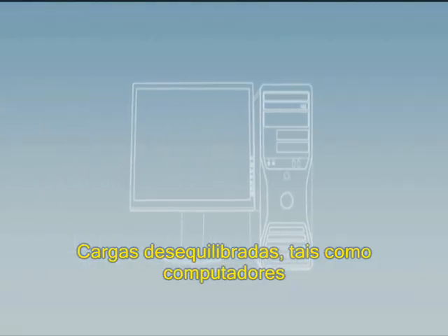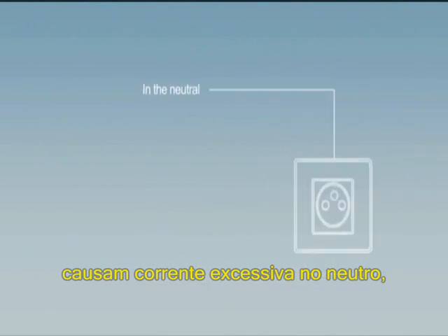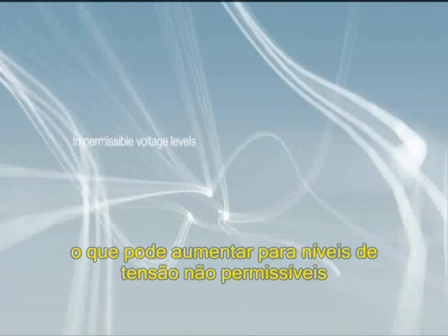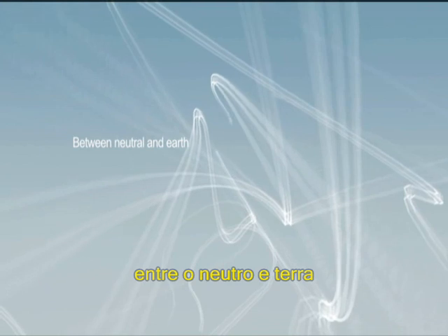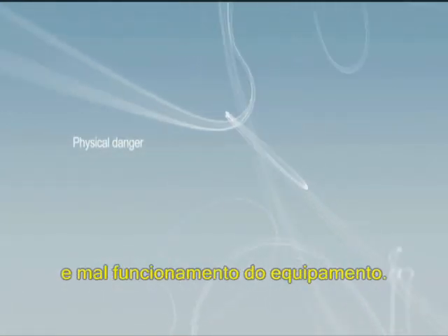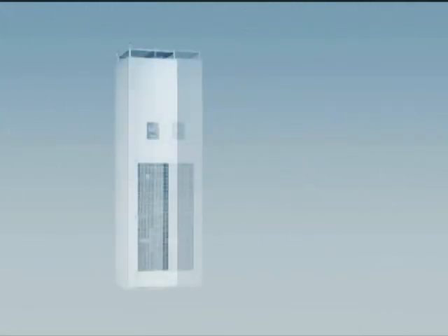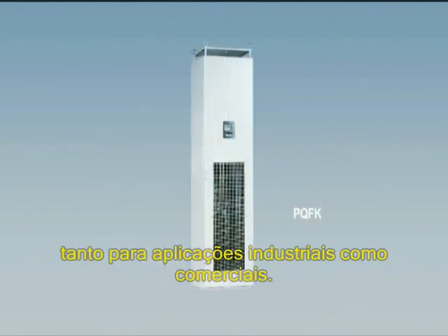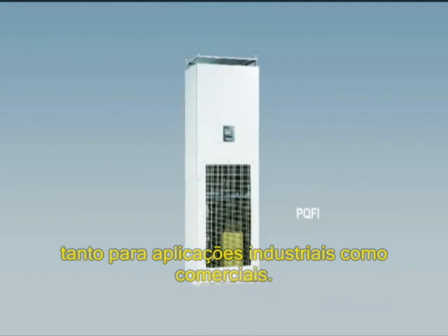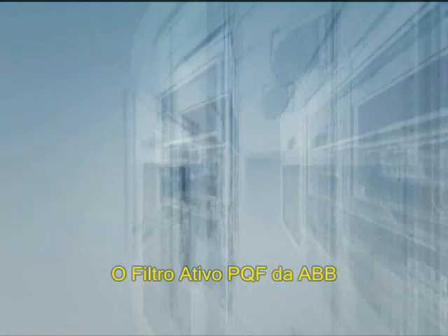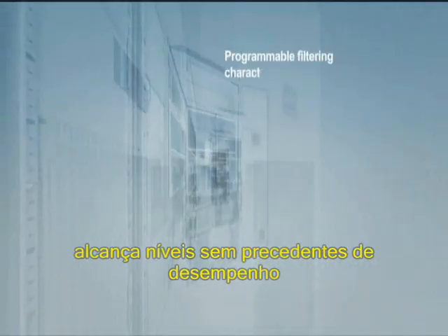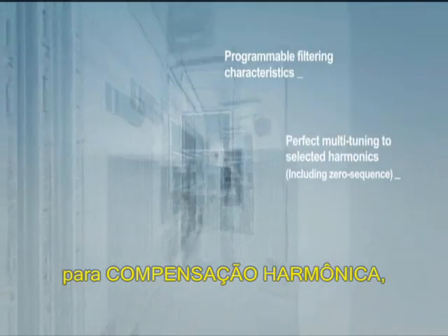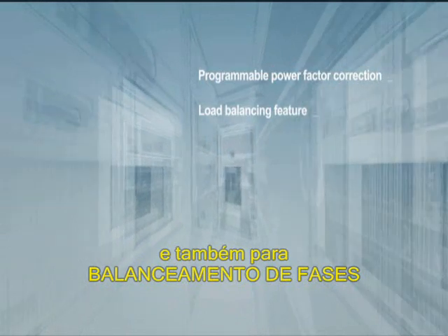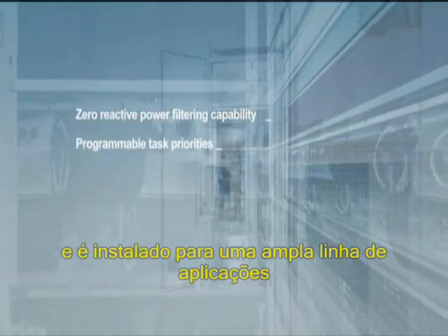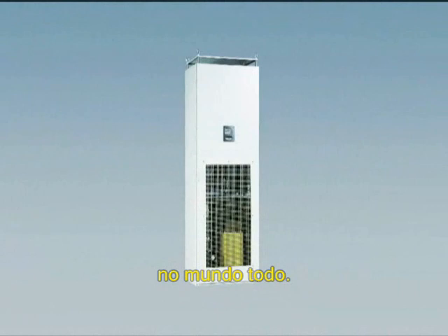Unbalanced loads such as PCs cause excessive current in the neutral, which may give rise to impermissible voltage levels between neutral and earth, and may result in physical danger and equipment malfunction. ABB is at the cutting edge of active harmonic compensation systems for both industrial and commercial applications. The ABB active filter PQF reaches unprecedented levels of performance for harmonic compensation, reactive power and load balancing applications, and is installed for a very broad range of applications worldwide.